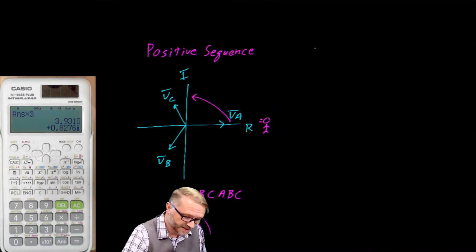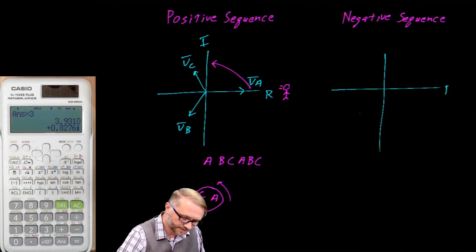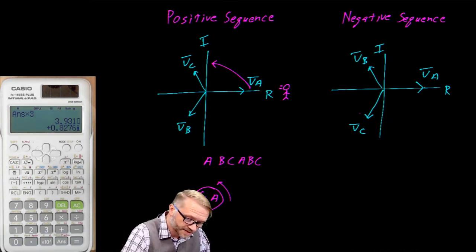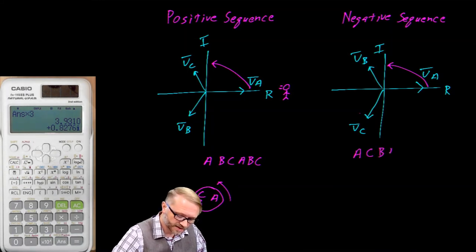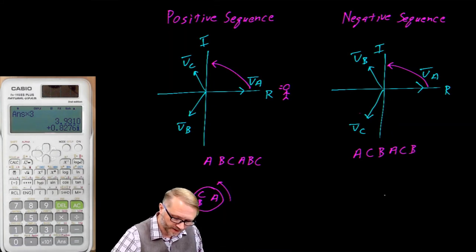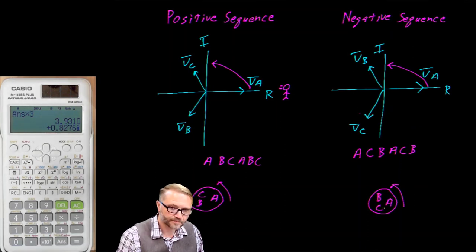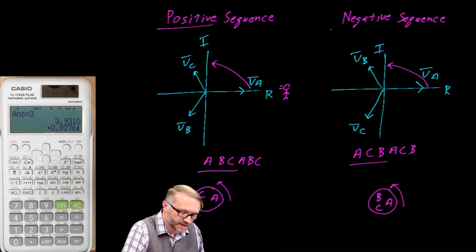There's nothing that says we can't have a negative sequence. On the complex plane, we again place the A vector at 0 degrees, but this time we swap B and C: C is at negative 120 and B is at positive 120. As the vectors rotate, you see A, C, B, A, C, B. We call this the ACB sequence — or negative sequence — as opposed to the ABC positive sequence. Why do you care? First, consider a motor connected to this three-phase system.